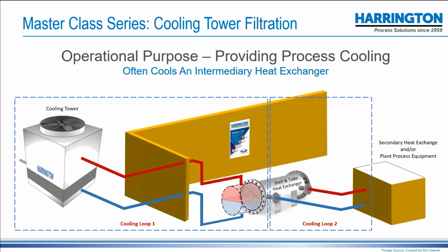Now, the image you see here is a shell and tube heat exchanger. There are other kinds of heat exchangers. There's flat plate and all kinds of configurations. This is by far the most common. And so you have the cold water coming in from the cooling tower to a baffled system. And then you can't see it in this image, but there are tubes that are U-shaped that run through this with baffles inside of the heat exchanger. And then hot plant water is pumped in, cold water pumped out to the plant, and hot water coming back in from the plant. And then it goes to the top side and back to the cooling tower.